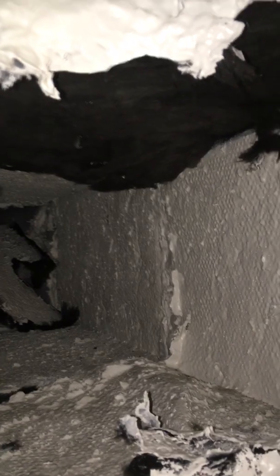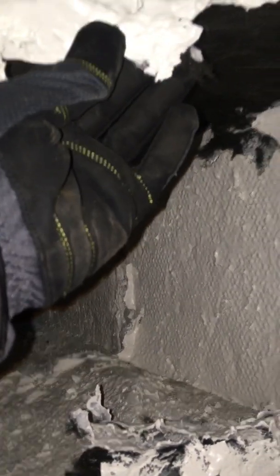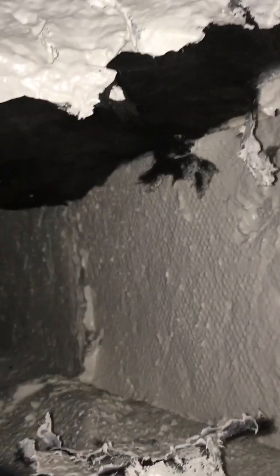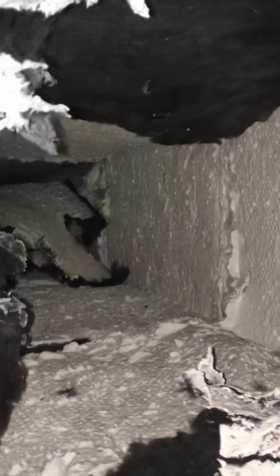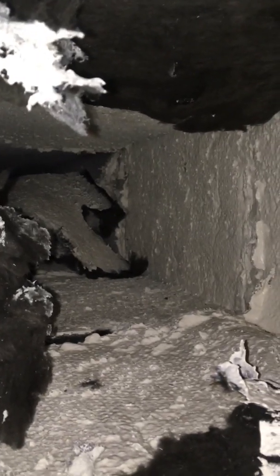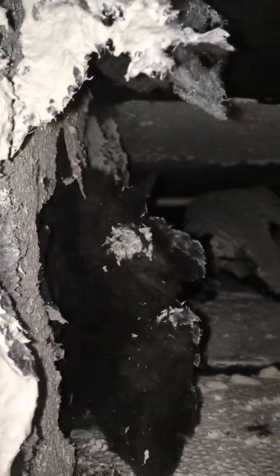This fiberglass has been de-laminating, coming unglued from the sheet metal for many years. It's past its design life. A decision was made to paint over this loose, deteriorating fiberglass insulation with a white latex paint. And that's what was done. It was not a good decision.